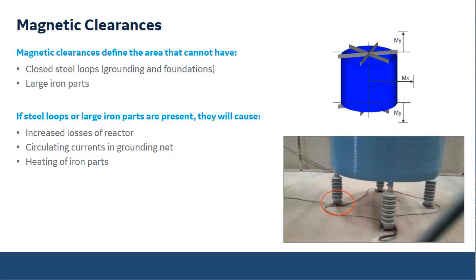So the magnetic field, as I mentioned on my first slides, depends on the current that's flowing through the reactor, the impedance, or basically the power rating of that coil. We are always going to provide you the magnetic field clearances with our proposal and with our drawings. This is something that we must provide because there is no simple way for you to calculate it. Well, yes, there is a way: there are pages and pages of formulas, but basically this is what our software is doing for you. We get your specifications, we calculate it, and we give you back the magnetic clearances.